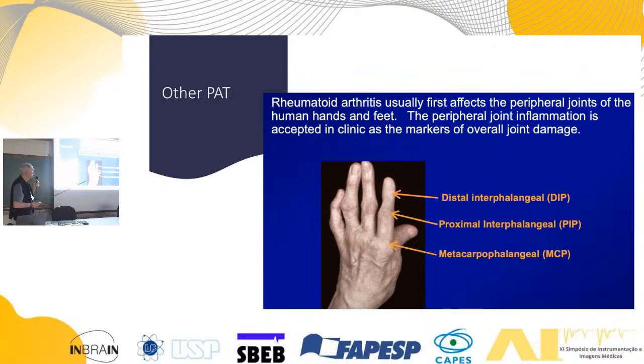I wanted to just mention a little bit more on photoacoustic tomography, where you're using light. You send a pulse of light in, it heats the tissue. You can heat dark tissues more than other tissues. You can heat oxygenated blood with one frequency of light better than you can with another, and deoxygenated better than with other frequencies. So if you use at least two frequencies of light, you can theoretically distinguish oxygenated from deoxygenated. But even then, it's a little bit hard because most people don't correct for the fact that you've got an inhomogeneous light field, and it's different in homogeneity for the different frequencies. So that needs to be done carefully, and one needs to look and see whether they're being honest about the claims.